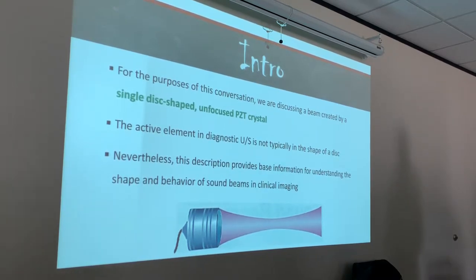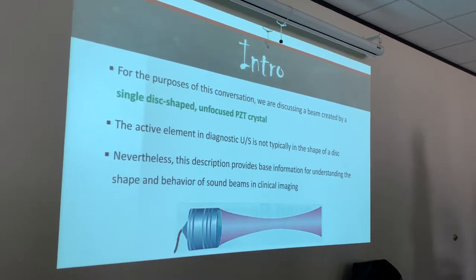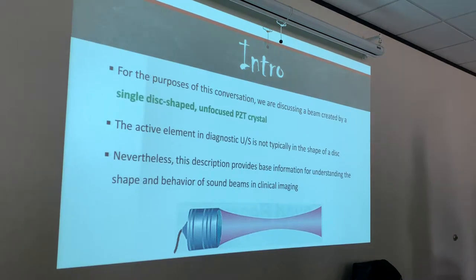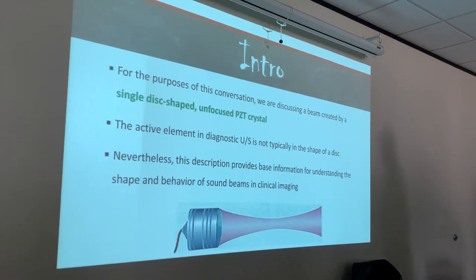We're going to talk about it from that aspect because you can also apply that to phased array transducers, which means they have multiple elements. The active element in diagnostic ultrasound is not typically the shape of a disc — it's usually the shape of the transducer face itself, the scan head itself. On a linear probe, it's usually a whole bunch of rectangles lined up across it. Nevertheless, this description provides base information for understanding the shape and behavior of sound beams in clinical imaging. So for the purpose of this conversation, we're talking about single, disc-shaped, unfocused PZT crystals — one active element — even though we know in a regular ultrasound transducer there are hundreds of active elements.